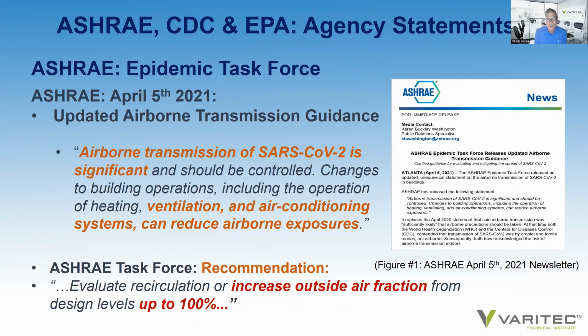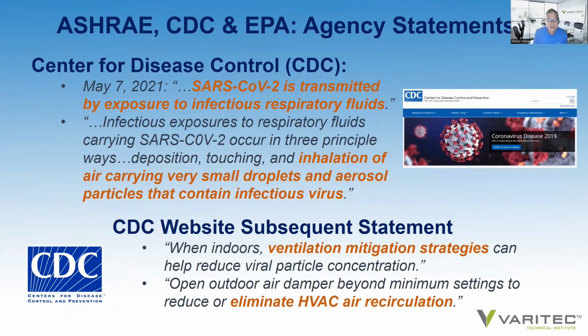On April 5th, 2021, ASHRAE's Epidemic Task Force issued this update: airborne transmission of SARS-CoV-2 is significant. Consequently, ventilation and air conditioning systems can reduce airborne exposures. An ASHRAE task force recommendation is to increase the outside air fraction rates from building design levels up to 100%.